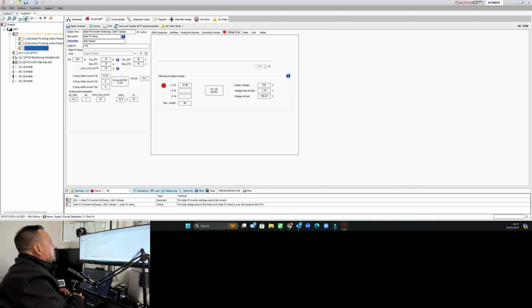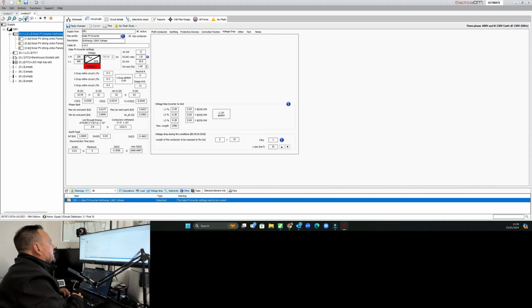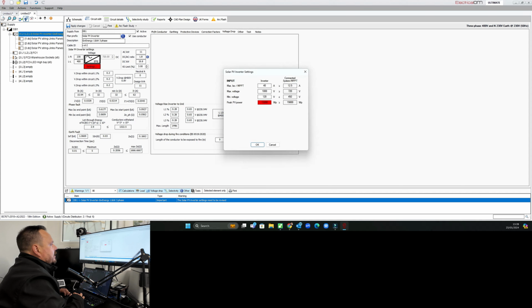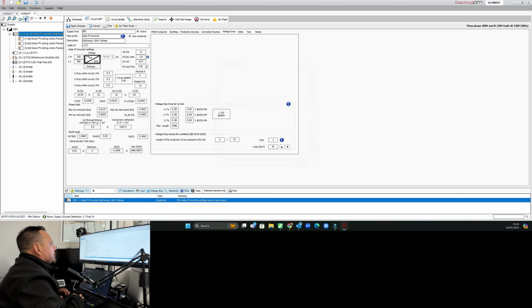You can see the voltage drop comes up as a problem again, and that's because we have popped another size inverter on. So you can see we've got that red warning on here. So we're going to say our PV peak, we'll just set it to 25 kilowatt. So we're way above now, so it will happily run that across all three phases. So we can see our DC-AC ratio is 1.8.